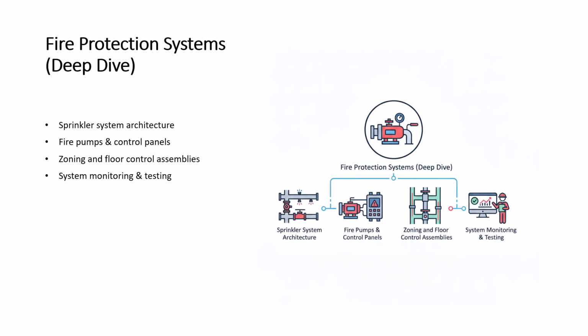Then come the fire pumps and control panels. It is the main fire pump that we have decided based on our hydraulic calculations, how it is going to operate and what it must comprise to maintain our specified flow and pressure. Then there is the part of our control assemblies. Whatever we are going to do with our system, we will define the zones for each level or each specific segment, and we will provide zone control valves, so that in case of an event in that specified zone, only that zone control valve will open and start providing all the water flow to the specified area of the zone.